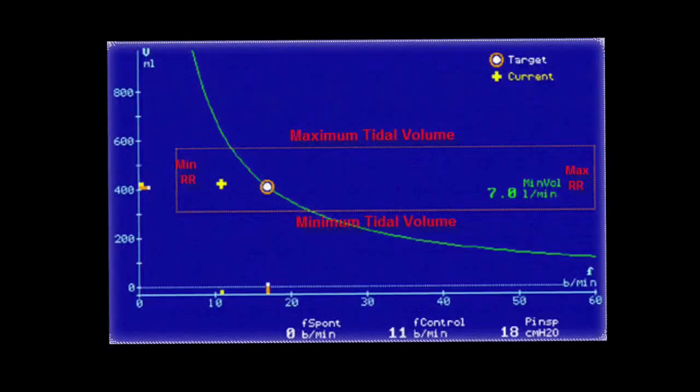In an optimal targeting scheme, the ventilator automatically adjusts the targets to either minimize or maximize performance characteristics. As you can see with ASV, it's trying to minimize lung injury. It's trying to maximize ventilation. It's trying to minimize rapid shallow breathing, and it tries to minimize intrinsic PEEP. And it tries to provide a ventilatory pattern, the least work of breathing, to the patient.